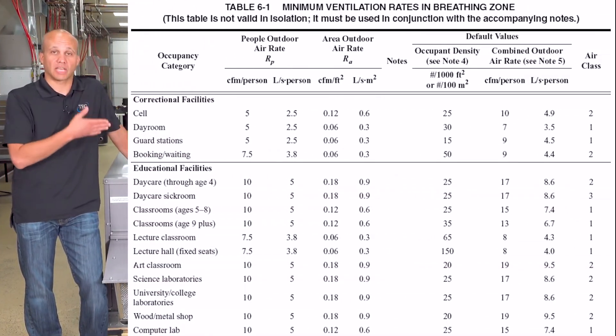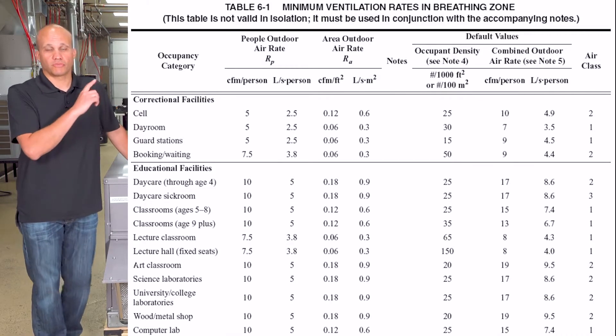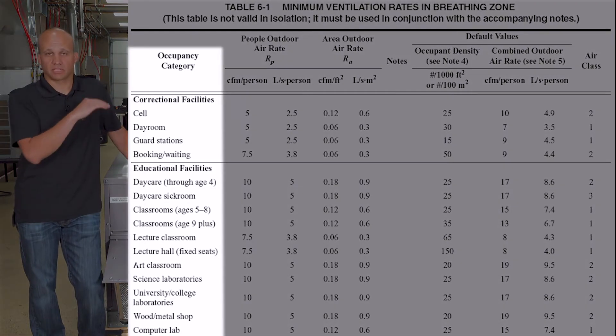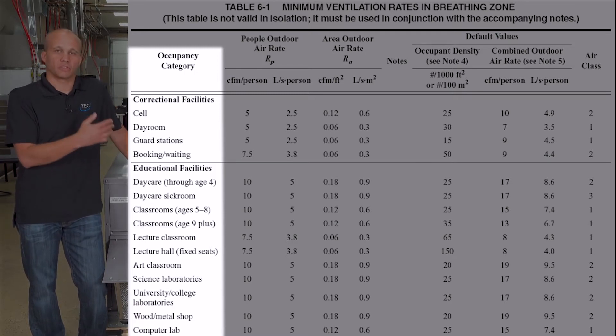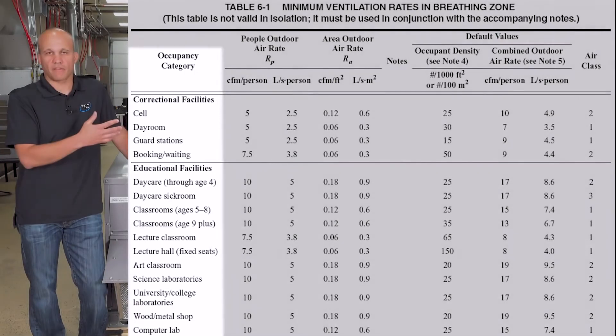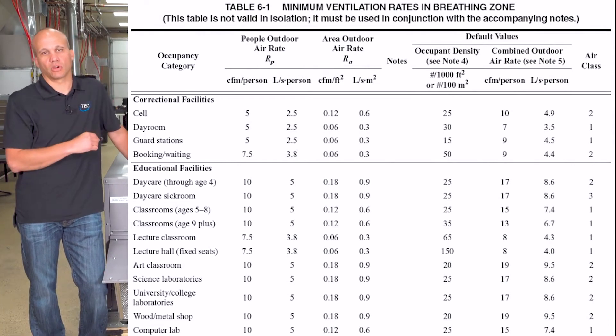We're going to take a look at this table here — this is just page one of about five tables. What you do is find your specific type of building, because it's a little different: a school needs a different ventilation rate than an office building would. So you find the type of building you have. We'll use an office example. Most of the columns you're going to ignore because they're metric — you only pay attention to two columns.